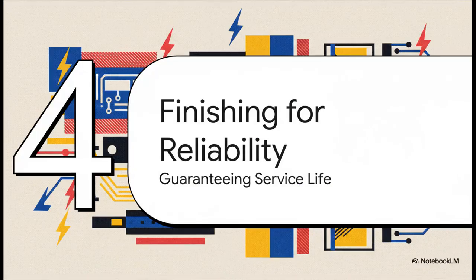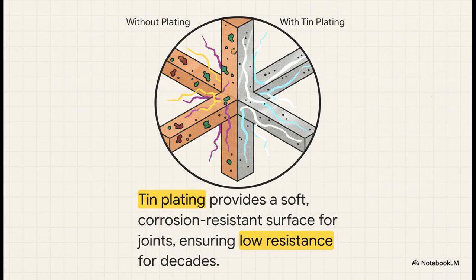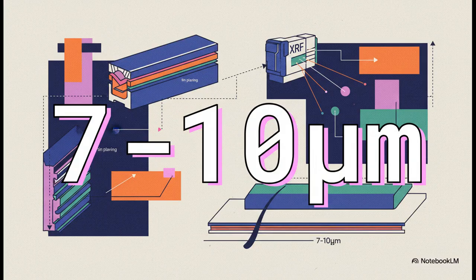Okay, let's move to the final stage, finishing for reliability. This is where we take that perfectly formed piece of metal and get it ready to survive decades of relentless work inside that transformer. It's the final touches that really guarantee performance for the long haul, especially at the joints where bus bars connect. By adding a super thin layer of tin plating, you create a surface that's soft and won't corrode. That means you get a perfect electrical connection with super low resistance, one that's not going to degrade over time.